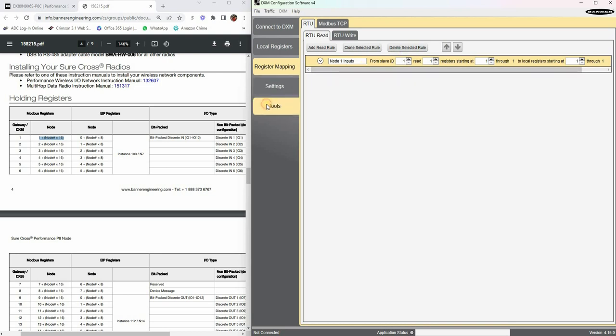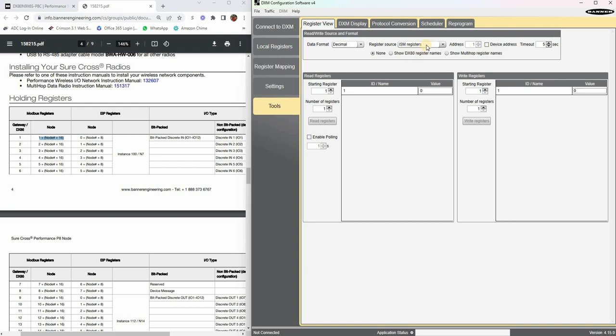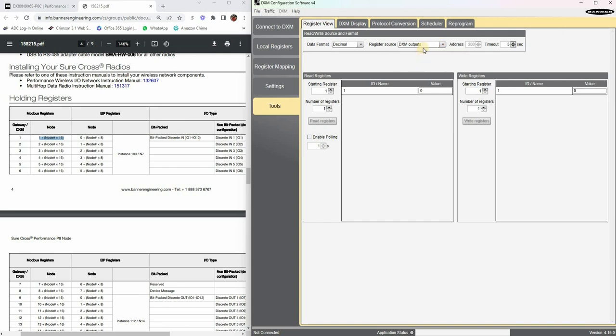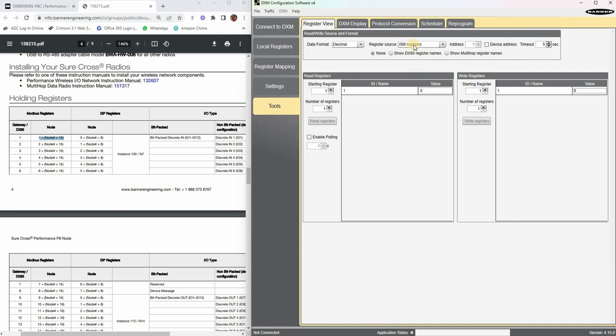Here under tools, under register source you want to look at, for example, if I'm using my ISM registers which is the radio layer, you'll notice that the address is 1, which is what we're referencing right now. If you had DXM outputs physically on your gateway, then those outputs would be on slave ID 203. So this is a good resource to let you know what slave ID you're under. We do have some display registers and those are on 201, and then our local registers are located on address 199. In this case we're just going to bring all of those radio node registers into the processor, into the local registers of the DXM.